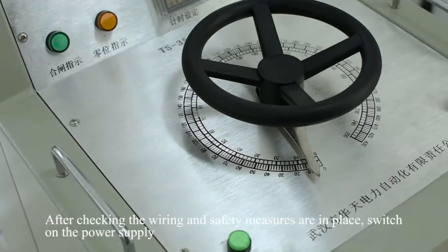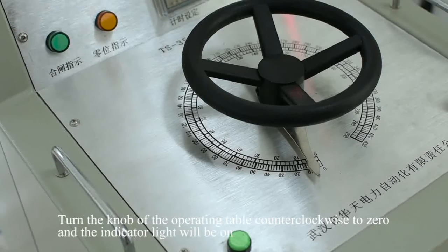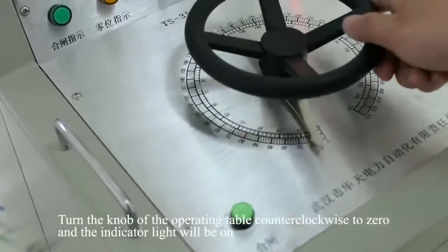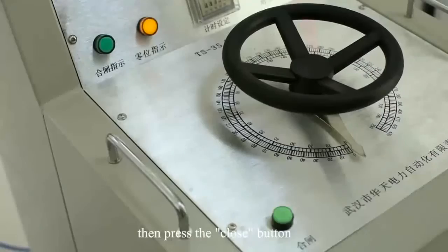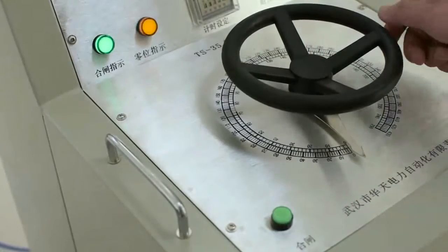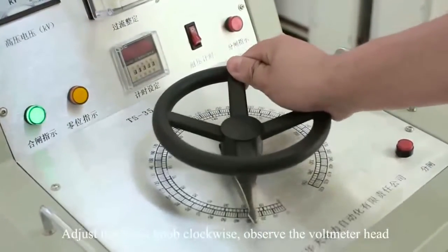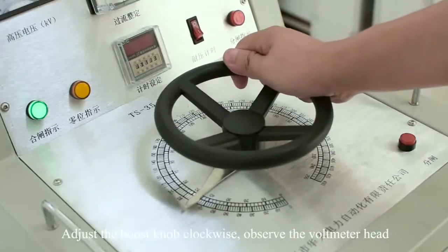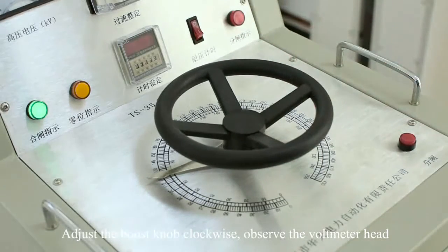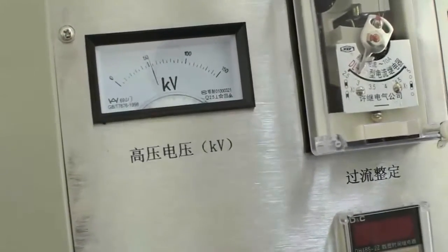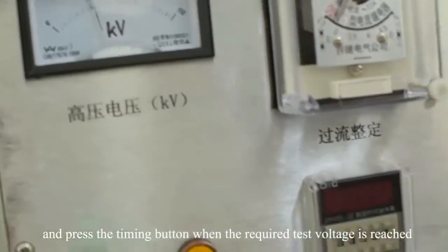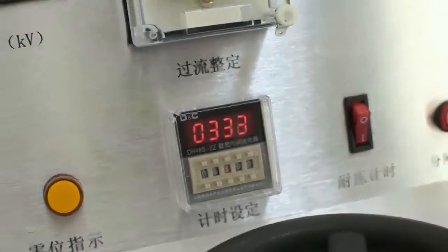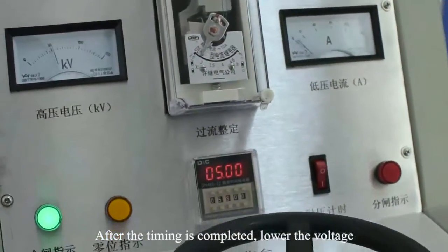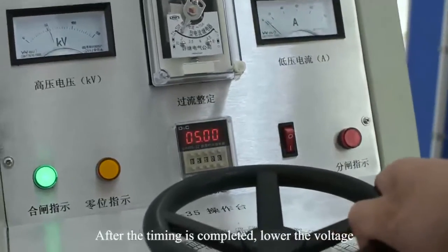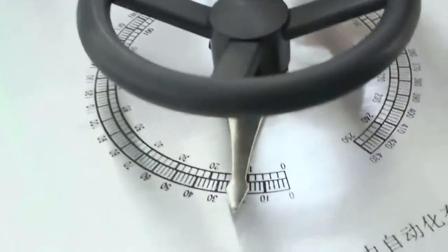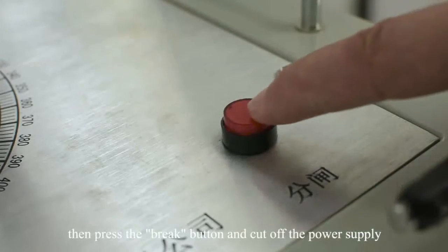After checking that the wiring and safety measures are in place, switch on the power supply. Turn the knob of the operating table counterclockwise to 0 and the indicator light will be on. Then press the close button. Adjust the boost knob clockwise. Observe the voltmeter head. Press the timing button when the required test voltage is reached. After the timing is completed, lower the voltage. Then press the break button and cut off the power supply.